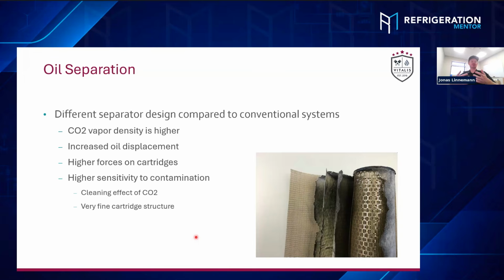And the high pressure and the high differential pressure, while the oil cartridge is clogging up, create a very high force on that cartridge. So that's why you sometimes see those cartridges exploding, basically. And that's one check that you need to do as a technician. You need to check what your inlet pressure is, what your outlet pressure is, and what that differential is. This one here would be zero because there is nothing there. So if you get zero, it's bad.